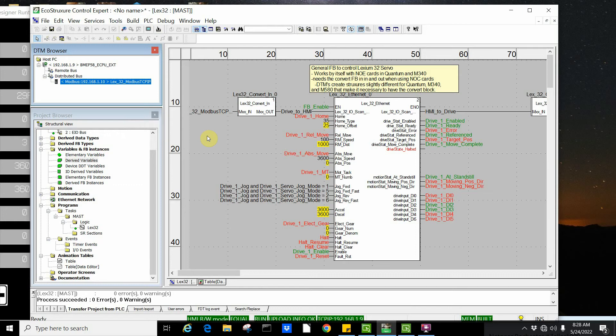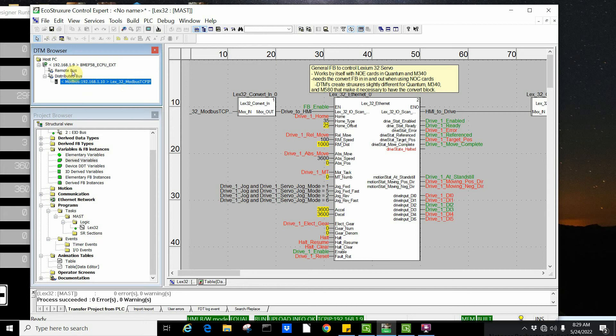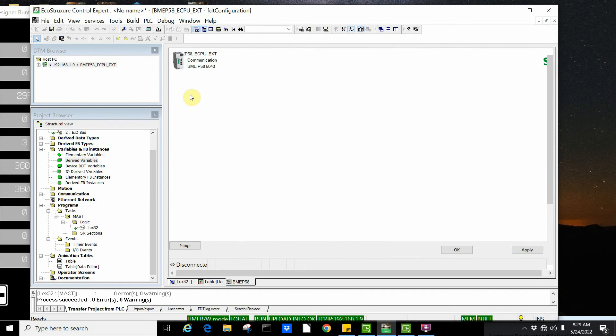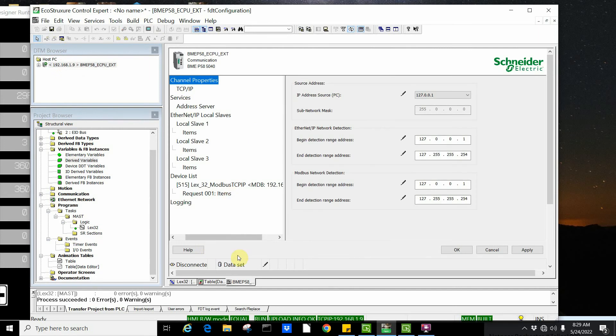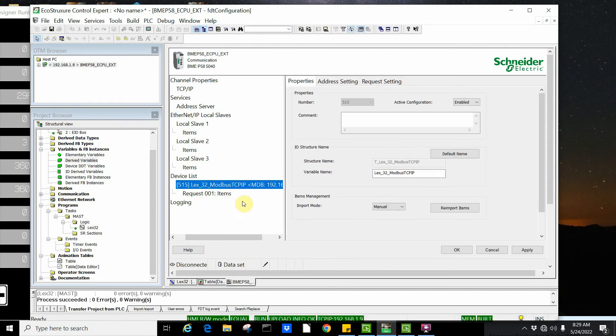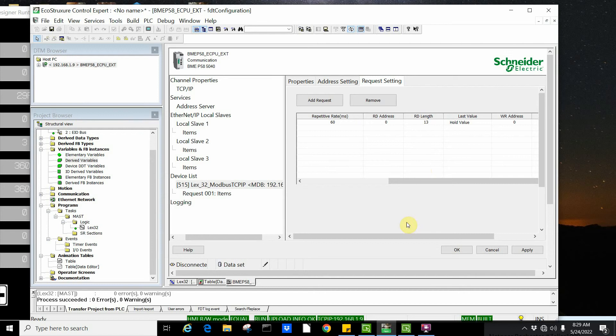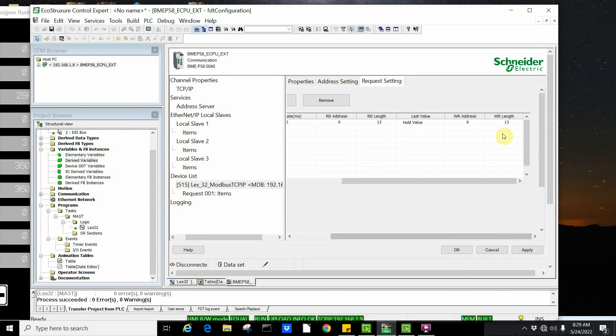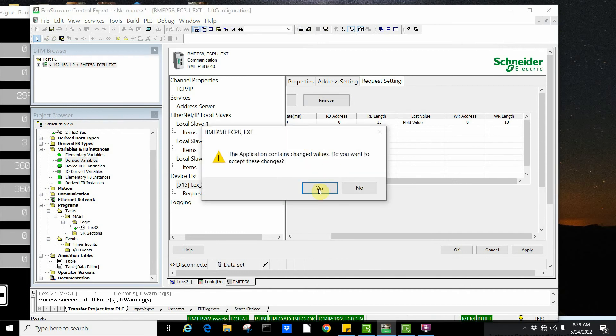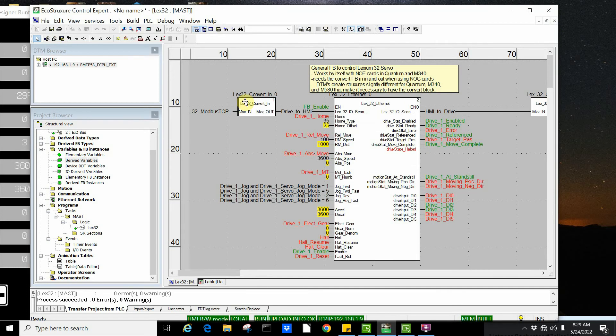I prefer to use SoMove separately to configure the drive and then just configure the application for this. To configure the servo drive, we double-click on it. We come down to the device and you can see we gave it the name Lex 32 Modbus TCP IP, and we simply ask for 13 words reading and 13 words writing. Depending on your application, you could actually look for 13 to 19.